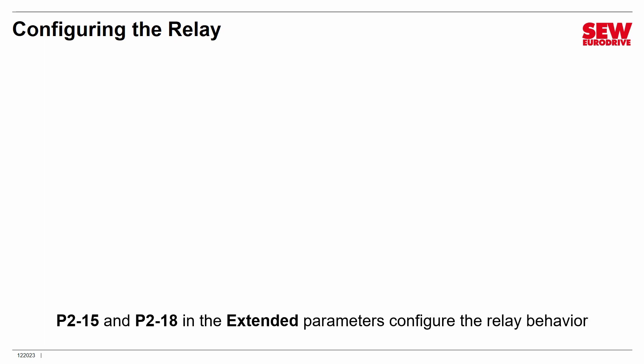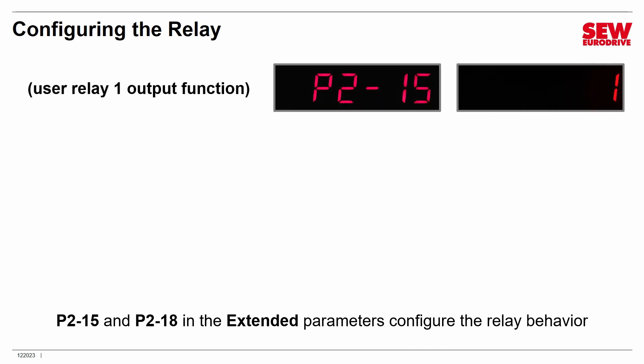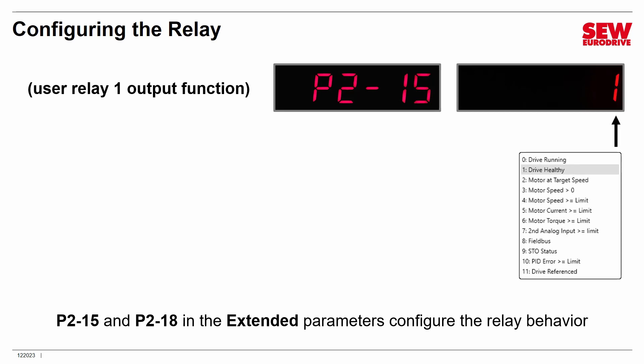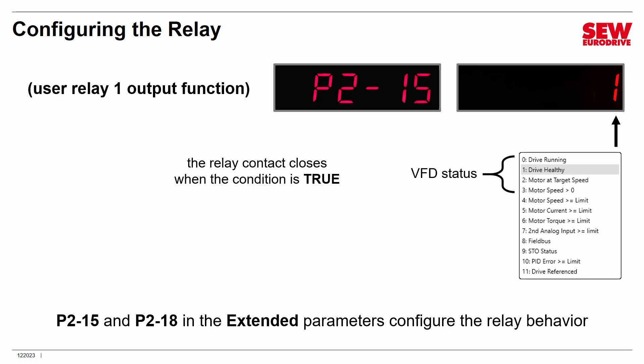Parameters 2-15 and 2-18 in the extended parameters configure the relay behavior. Parameter 2-15 is for relay 1 and 2-18 is for relay 2, but they are identical in what you do with them. The default is option 1, which is drive healthy. The top four options indicate VFD status, which is very useful when communicating back to a controller. The relay contact closes when the condition is true.